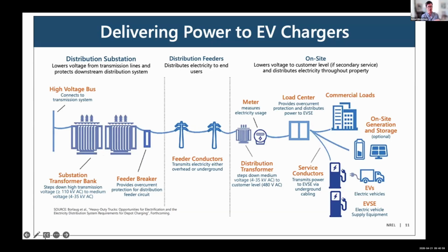Typically the utility owns everything up to the meter, and the customer is responsible for everything downstream of it in a typical project—the load center, conduit, service conductors, the kind of work a traditional electrician can handle. For an EV charger type project, the utility might place a couple of poles, some secondary or primary feeder to a pad-mounted transformer, and a meter, while the customer handles the rest. If you're looking at a substation upgrade or anything beyond a reconductoring on a feeder, the project's probably not economically possible. But the good news in this region is we often have enough capacity in many places, though not all, to support these types of loads without major upgrades.